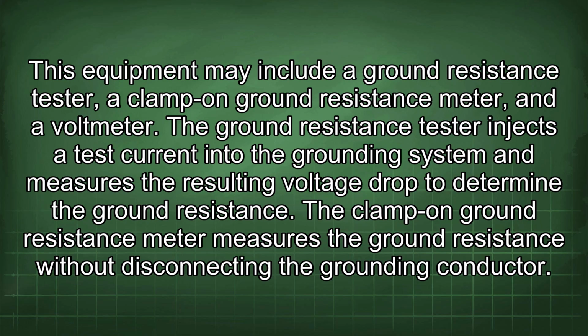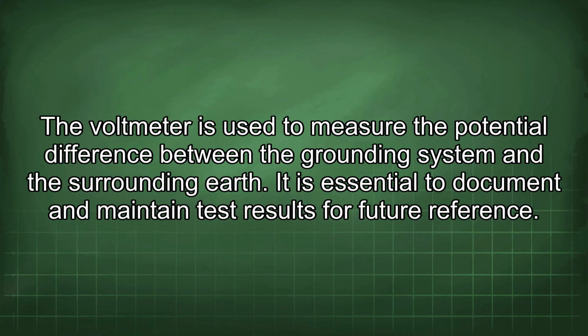The ground resistance tester injects a test current into the grounding system and measures the resulting voltage drop to determine the ground resistance. The clamp-on ground resistance meter measures the ground resistance without disconnecting the grounding conductor. The voltmeter is used to measure the potential difference between the grounding system and the surrounding earth. It is essential to document and maintain test results for future reference.